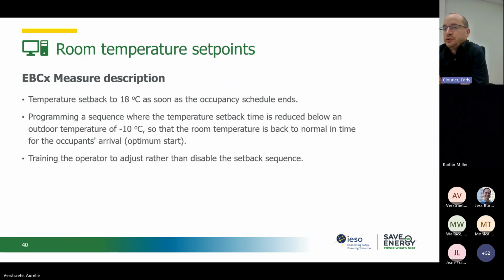However, the system was programmed so that when the outside temperature was under -10, the room temperature was set back to normal earlier in the morning to make sure that when the occupants arrived at their desks, the temperature was close to normal. And of course, it's always appropriate to train the operator to adjust the way the system is doing the setback instead of just deactivating it.